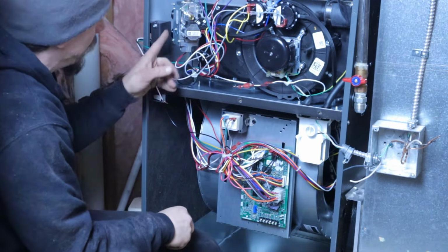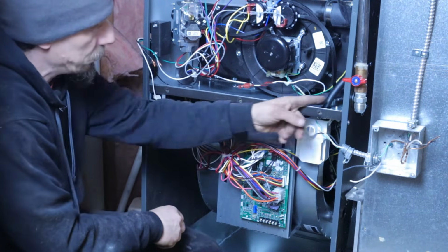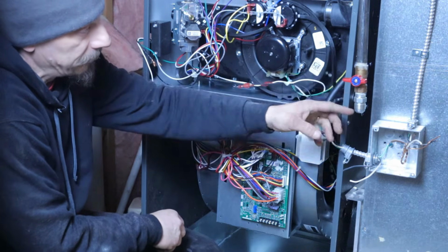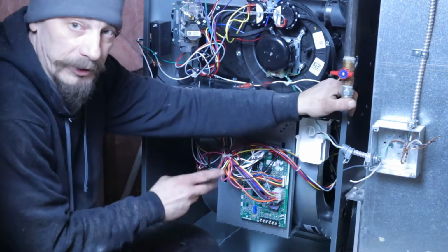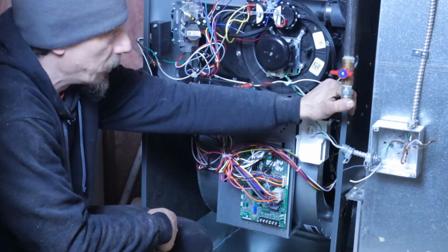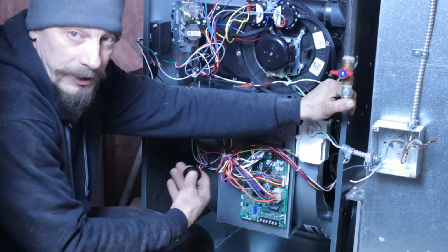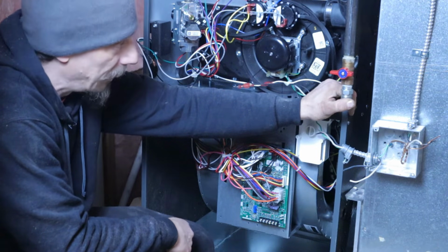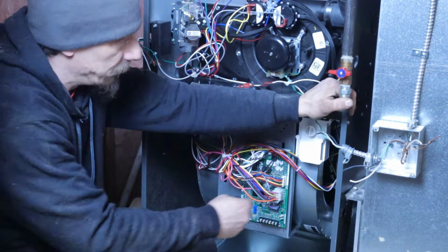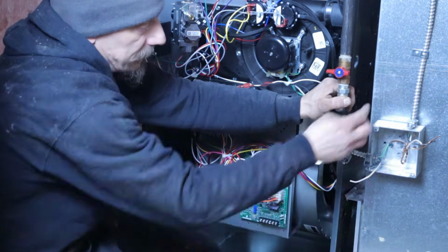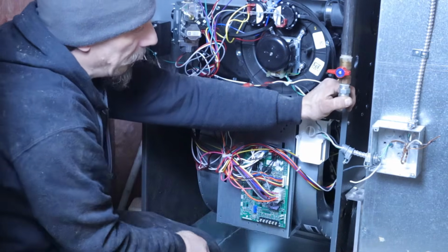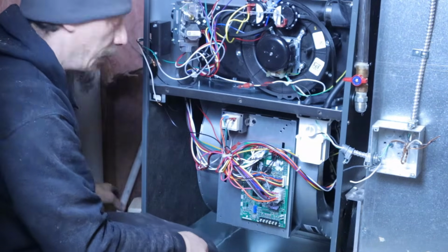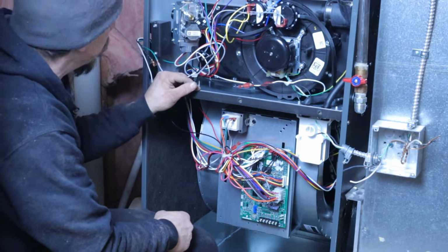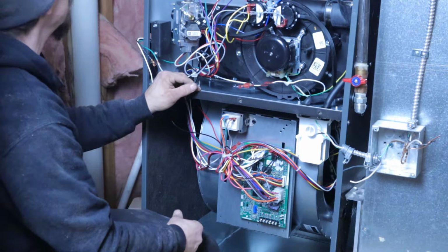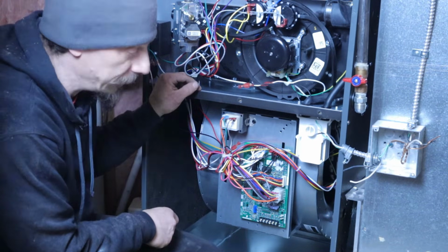We're going to come across, this is our gas valve here. We're going to come down straight across, come right out here and reconnect our gas pipe here. We're going to do all that hard pipe. It's not code here to be using flexible pipe. We're not in an earthquake prone area or anything like that. And for our electric, we're just going to come right back off the box and in here. New switch, new outlet. That's going to be for our condensate pump. Hook up the flue pipe, the low voltage wiring, and get the PVC back in. We'll be ready to fire it up.